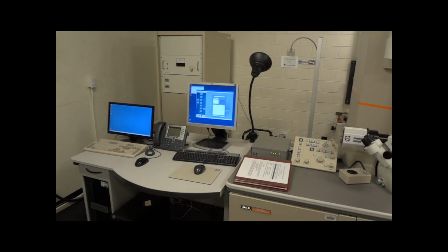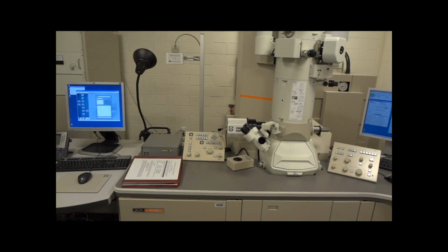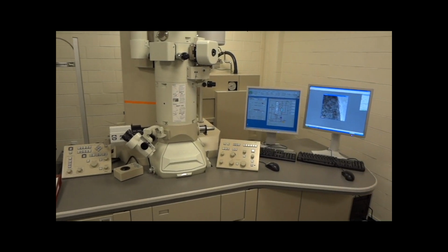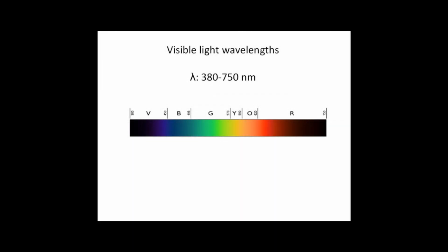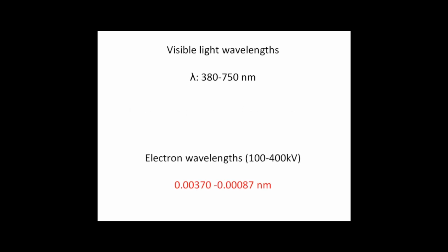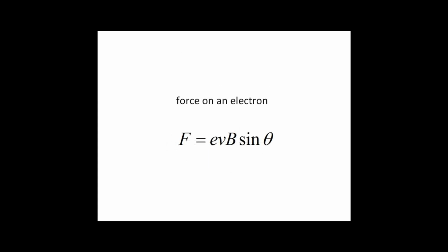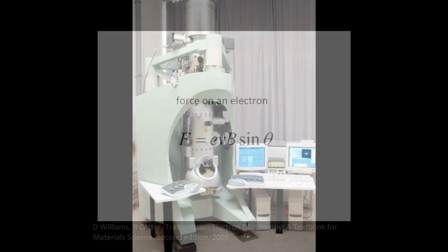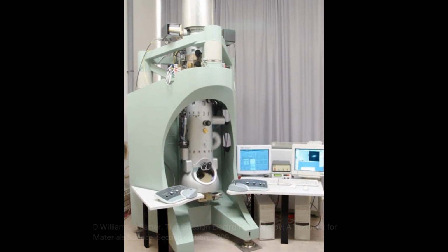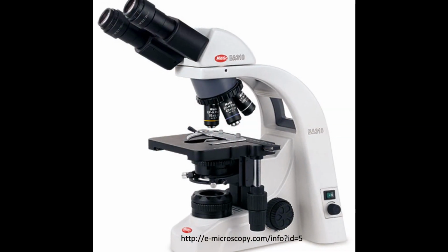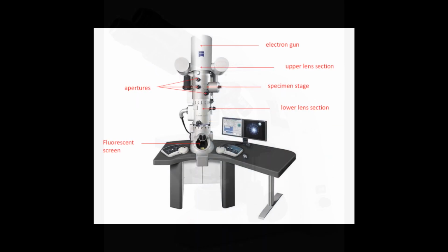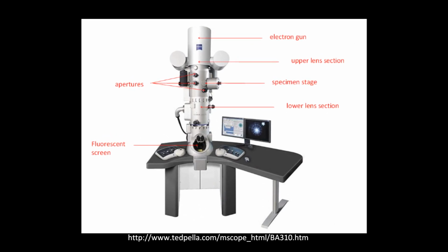Electron microscopes were developed due to the limited image resolution of light microscopes, which is imposed by the wavelength of visible light. TEM uses electrons instead of visible light. This microscope is only possible because of the electron's wave-like behavior, with a wavelength substantially smaller than that of visible light. Electrons can be controlled by magnetic fields and can interact with materials, producing a wide range of signals that can be detected. In general, a TEM can be roughly thought of as a visible light microscope, which employs electrons instead of visible light, and a system of lenses to control all the basic operational functions of the instrument.